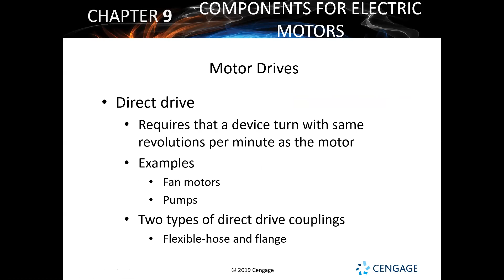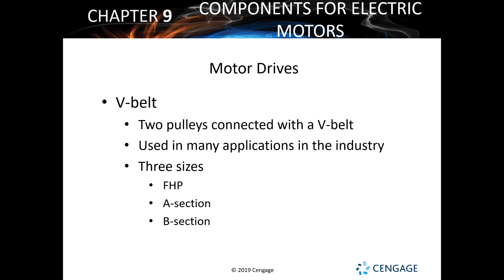Again, for motor drives, if it's a belt system, it's a V-belt. That's what you're going to be using. You've got 3 sizes usually, FHP, A, or B, and that's pretty much what you're going to be seeing most often in the industry. This is what's used typically for rooftop package units. The motor itself will be on a track that you can loosen with the nuts on the bottom of it, and as you tighten and loosen them, it'll move forwards and backwards. So you can bring it up, loosen the belt, take the belt off, put the new belt on, and then tighten it back into position and check the belt tension with a belt tension gauge to make sure that you've got proper tension in the system.